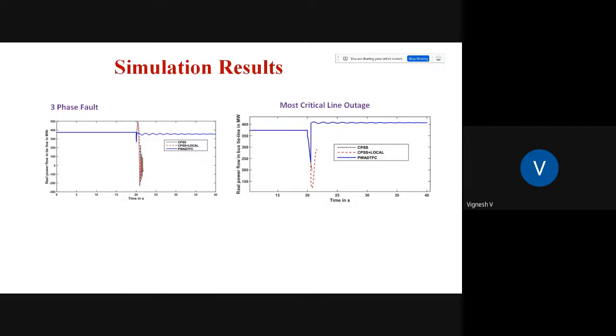Next slide, please. And so we validated the performance of the controller using some disturbances. We use a 3-phase fault and the most critical line outage fault. The most critical line is the line that goes from Neyveli to Sriperumbudur here. We made an outage of that line, and we could see that the conventional power system stabilizer and the local controllers are not able to damp out the oscillations, whereas the proposed controller is able to damp out the oscillations very fast. Even for a 3-phase fault, we could see that the other two types of controllers fail, whereas the proposed controller stabilizes the oscillations.